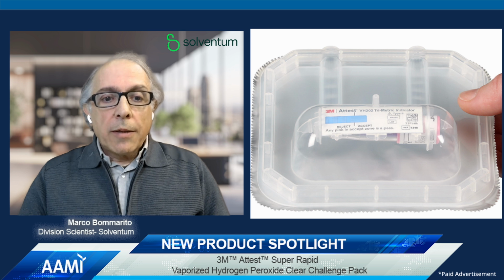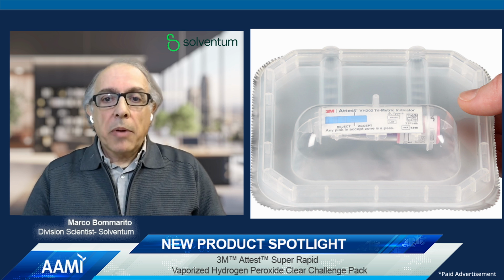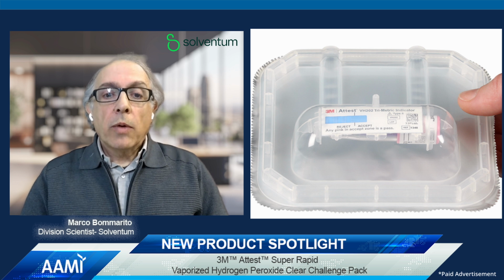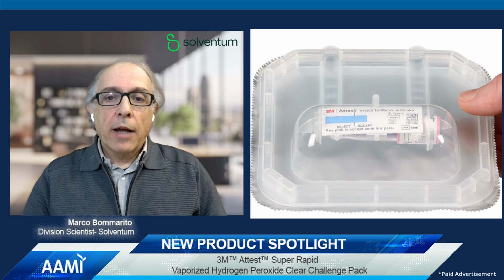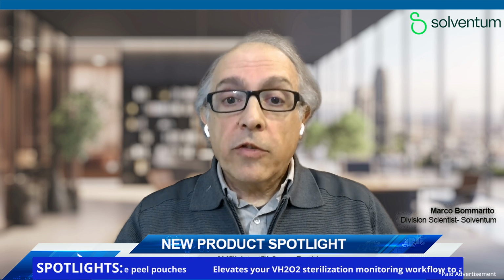Instruments. And so in listening to them, we identified a gap in the practice of sterilization assurance when we compare steam sterilization to vaporized hydrogen peroxide sterilization. In vaporized hydrogen peroxide sterilization, they didn't have a test pack, whereas in steam sterilization, a test pack or a PCD is used routinely. And so we created the first FDA-cleared process challenge device for vaporized hydrogen peroxide sterilization that is meant for routine monitoring. And it's in contrast to what they use today, which is a peel pouch. And they have to assemble that peel pouch. And that peel pouch in itself is not really a process challenge device because it doesn't really offer a challenge to the sterilant.